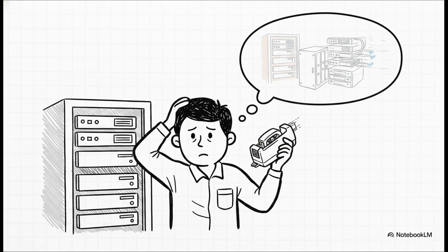Second, don't rely on your memory. Even if you've been to this exact data center ten times, re-verify those labels. These environments constantly change. Equipment gets swapped out during night maintenance all the time, and your memory might be visualizing a unit that got replaced three days ago. Remember the golden rule: if you spend ten minutes identifying an unmarked device, spend the thirty seconds to actually print a label for it.